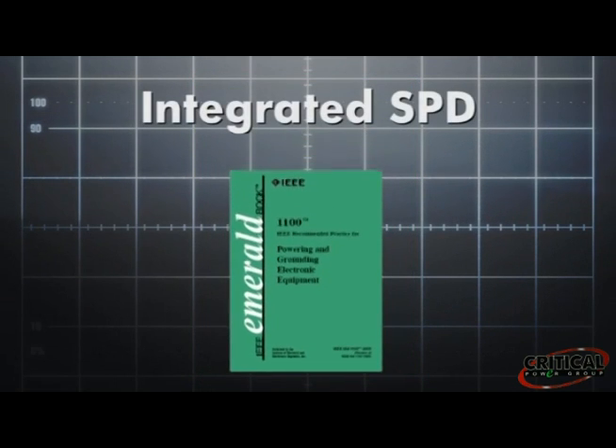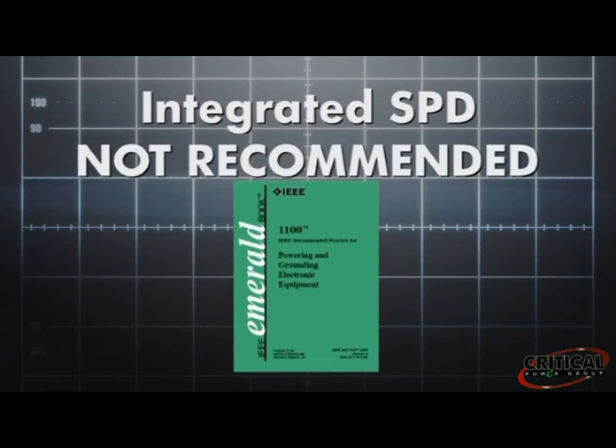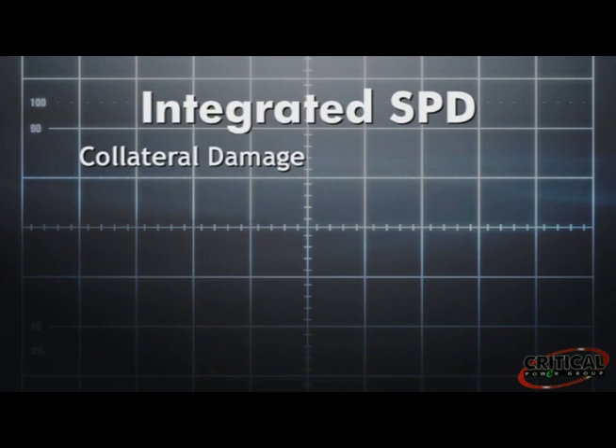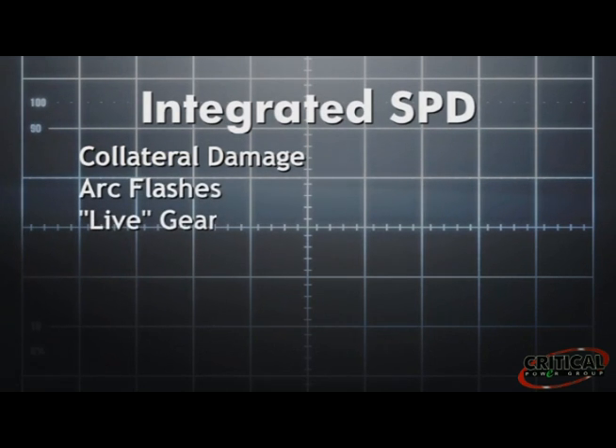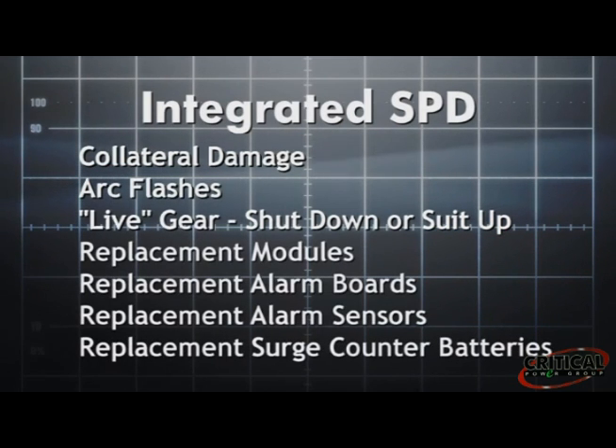states that integrated SPDs are not recommended because they greatly increase the risk of collateral damage caused by product failure and arc flashes. Internally mounted SPDs force employees to work on live gear, greatly increasing personal risk. Live parts are exposed every time a part is replaced or maintained. You either have to shut down or suit up. Secondly, internally mounted SPDs may cost less to install initially, but will result in higher replacement costs associated with replacing protection modules, alarm boards, alarm sensors, or any other failure of an internally mounted system.